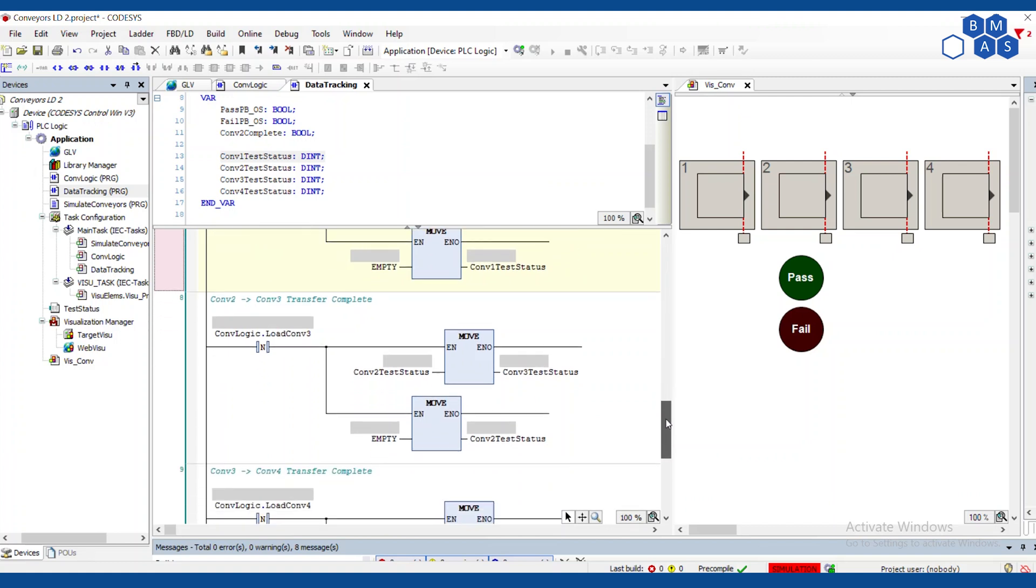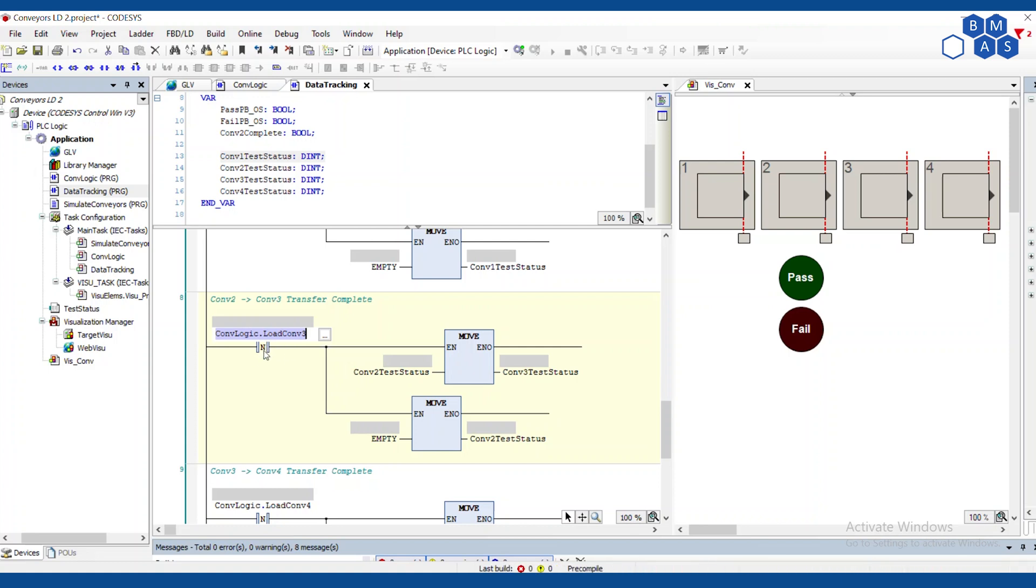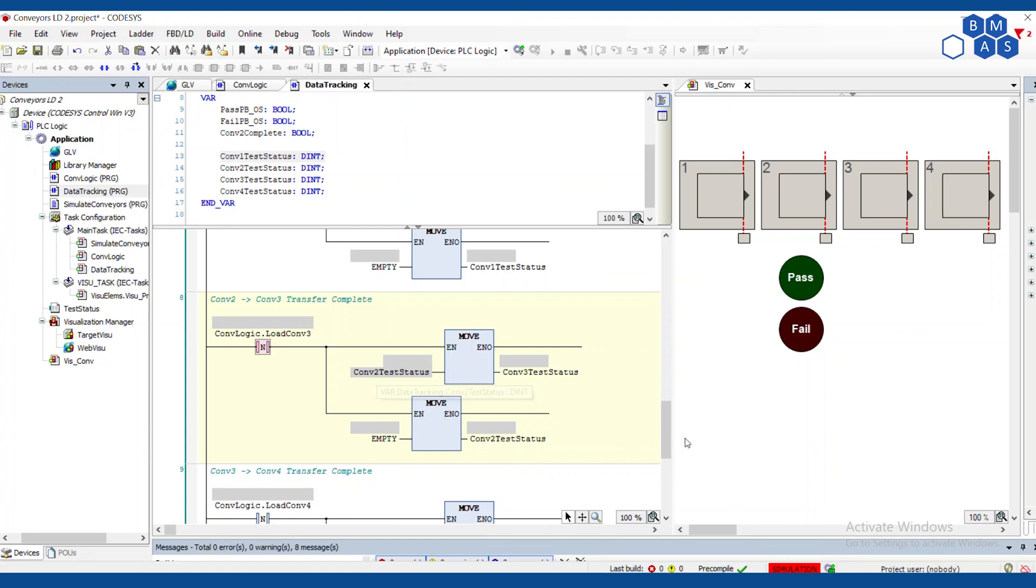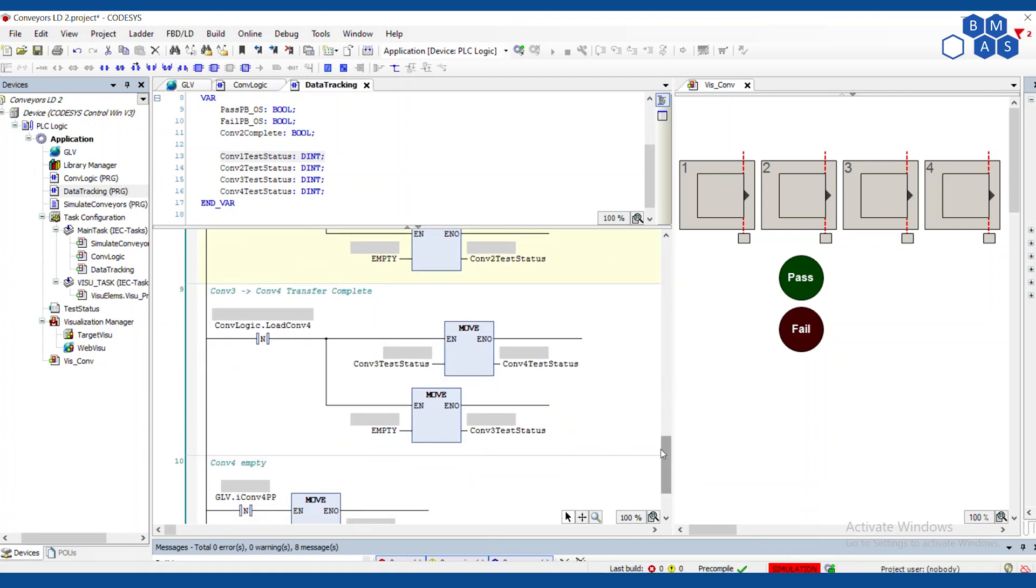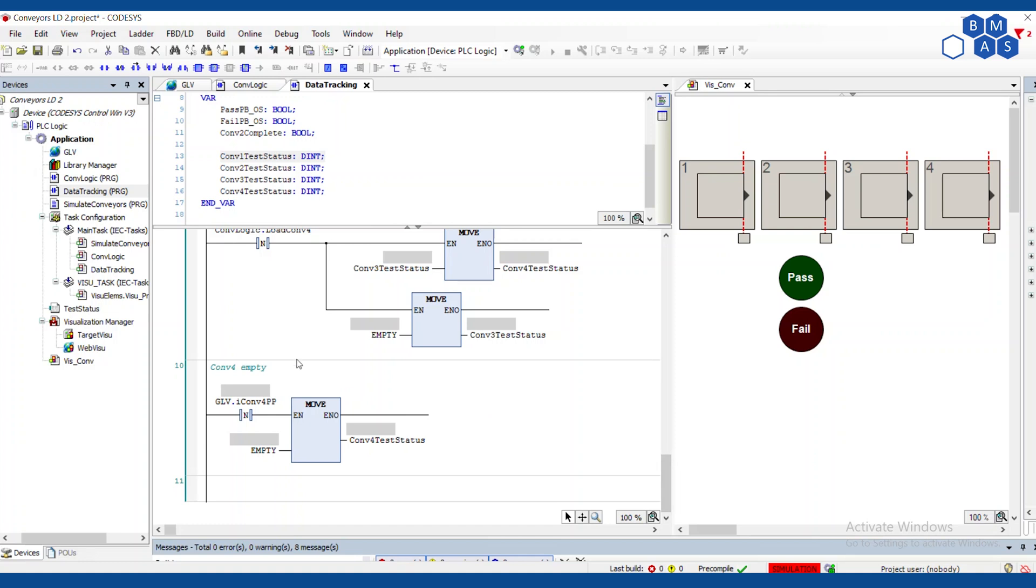And then rather than clearing out every little piece inside of a structure, you can just move that whole structure right into the status. So you'll see the same thing happening in all the other stations until again, we get to the end. So conveyor two to three, when loading conveyor three is done. So at the falling edge of that, we're going to move two into three, we're going to move empty into two. Conveyor three to four, same thing.